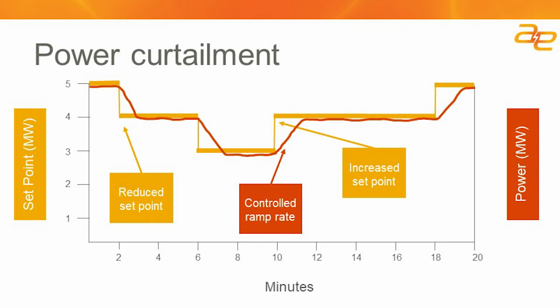Then the control system, as it commands the inverters, doesn't just send a new command at the new value and allow the inverters to step down quickly. It'll ramp the command down over some period of time. Typically 10% of the plant capacity per minute is the standard. So if it were a 5 megawatt plant, it would ramp at half a megawatt a minute. If you command a 1 megawatt change, it'll take 2 minutes to get from the previous set point to the new set point. That's kind of typical for the large generation industry. You may want it to run faster or slower. It's that slow transition of set points that allows the grid to work well with the solar plants, or the solar plants to work well on the grid.